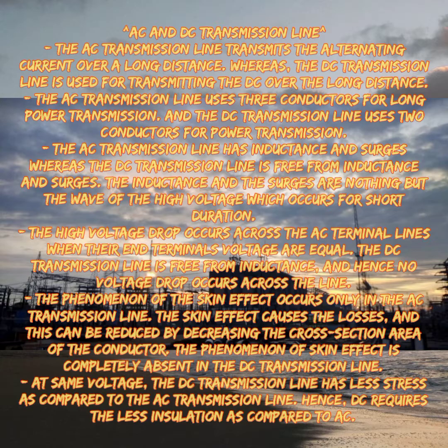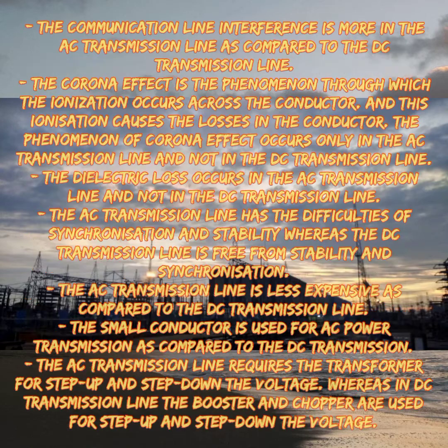At the same voltage, the DC transmission line has less stress as compared to the AC transmission line, and hence DC requires less insulation as compared to AC. In cost terms, building a DC transmission substation is very much higher when compared to AC. Then communication line interference is more in the AC transmission line as compared to the DC transmission line.